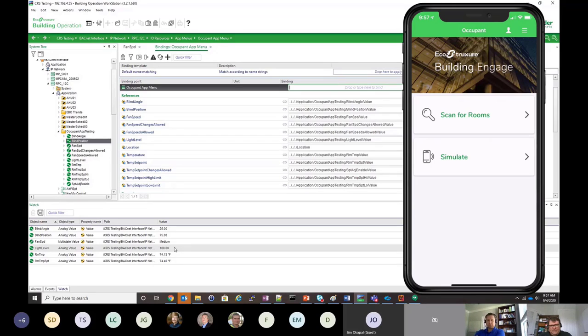As David Fisher presented in a past session, David, the living space sensor uses an HMI reference, right? That is correct for about 8 different signals. So you'd have to check the web help, but it's kind of the ones you would expect. The room temp set point, the room occupy override, and then the rest of them, I believe, are all connected room solution signals, so blind angle, lighting control, whatever. Cool. So set point change done through the living space sensor has the ability to go in and modify the value, but not hold the value captive.